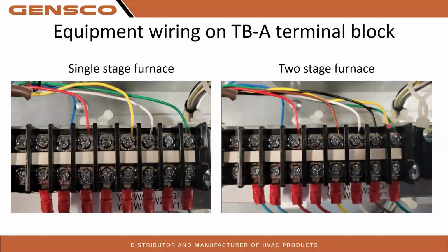So one of the things you guys can do to help clean this up is, we have our G and our Y together here on the G/Y1 terminal block. If you want to, do just a jumper inside your furnace and run a single wire to here. So put a jumper between your first stage and fan call inside your furnace, that would work as well, just as long as your G and your Y1 are tied together.